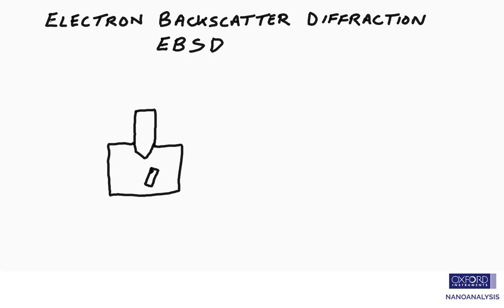Here is an SEM with an electron column and a sample shown in black. The sample needs to be flat and polished for EBSD, and we tilt it up to a high angle from the horizontal, typically 70 degrees.